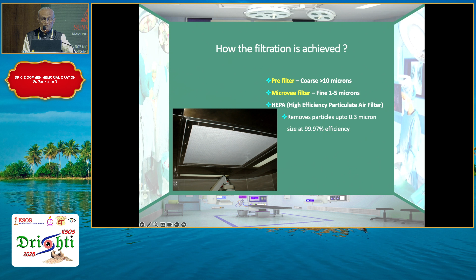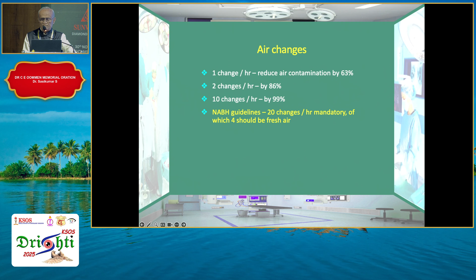Up to 10 air changes per hour are found to reduce air contamination by 99%, but NABH recommends 20 air changes per hour, of which 4 should be fresh air. If a laminar flow unit is not there, the flow at the surgical zone would be turbulent. A LAF unit distributes the air in a single direction to an area around the surgical zone at an imperceptible velocity of 0.1 to 0.3 meters per second. The flow is restricted to the surgical zone, which provides the room within a room concept. Contaminated air will not enter the laminar flow zone, which is the surgical zone.